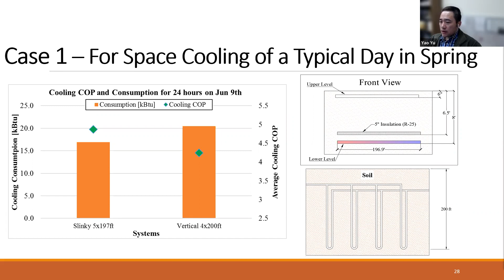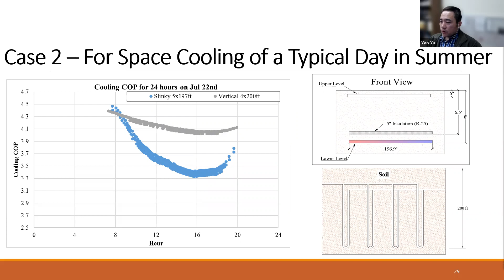And then for space cooling in summer, the heat pump using the lower loop can achieve a COP of around 4.4 in the morning and then drops to around 3.5 in the afternoon due to the ambient air environment, mainly including the ambient air temperature and solar radiation. Compared with the dual loop system, the vertical boreholes have higher cooling performance. As you can see, the COP is more stable for the vertical boreholes, changing only between 4.0 and 4.4.